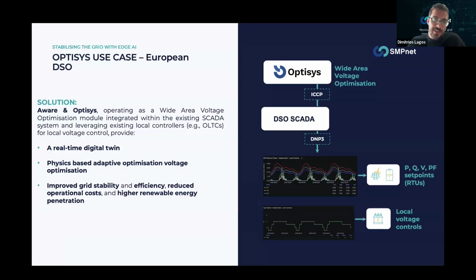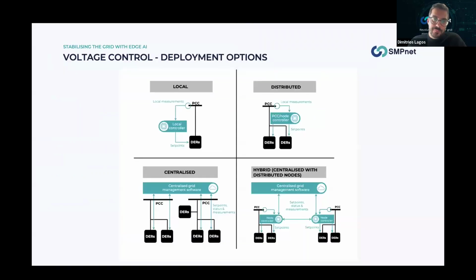So Optisys is managing the wide area voltage optimization through a real-time digital twin, a model of the network with a physics-based model with all the electrical characteristics of the network, that is updated with the latest status of switches to have the active topology on every Optisys run, and then performs an adaptive optimization of voltage using this physics-based model. And through that way, it can provide improved grid stability and efficiency, reduced operational cost, and high renewable energy penetration.